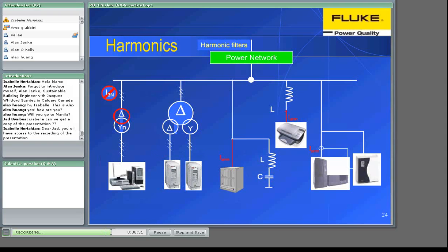Filters can be applied in order to remove unwanted harmonics. A passband filter is a device that passes frequencies within a certain range and rejects or attenuates frequencies outside the range. Thus, knowing the harmonic generated by a nonlinear load, it is possible to calculate an adequate passband filter in order to short-circuit and remove those frequencies. A low-pass filter is a filter that passes low frequencies but attenuates signals with frequencies higher than the cutoff frequency. Thus we will permit, for instance, the 50 Hz to pass through and stop higher harmonic frequencies.